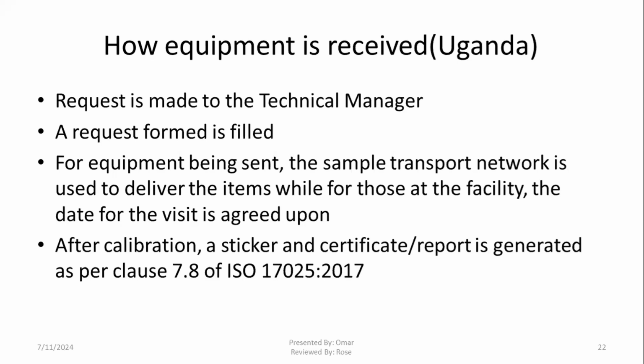And just a glitch on that clause, for example, you'll have a sticker that may not have the next due date, because the next due date must not appear on the calibration sticker unless it has been agreed by the customer. So if you have not agreed with the customer, then you must not put the next due date. And then also in the reporting or the certificate, they are well streamlined, well listed, what identification must appear on the report.